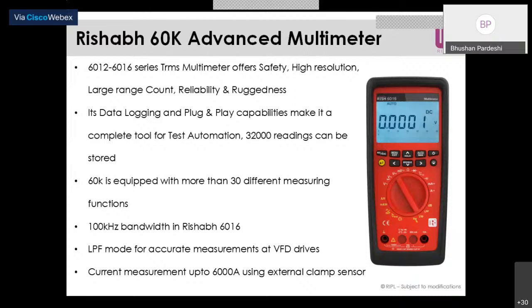Here you can see that the hertz symbol is there. This hertz symbol is nothing but the frequency. This data is basically used when motors and VFD drives are there, so harmonic content or higher frequencies are there to measure the pure waveform. This LPF mode is used to give the fundamental waveform voltage value, so for that purpose LPF filters are there.